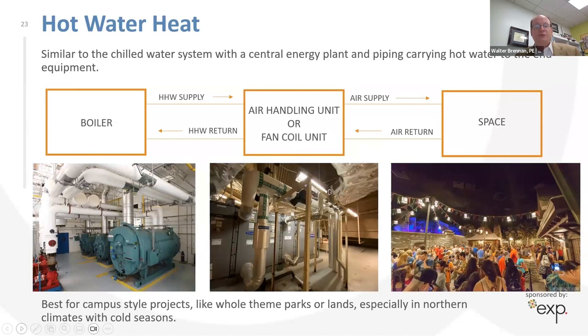Similar to the chilled water system, we also have a hot water system. We have a central boiler that heats up the water anywhere between 120 and 180 degrees Fahrenheit, runs it through an air handling unit. The heat gets taken off the air handler and dumped into your space so it stays warm. The hot water gets cooler, so we have to bring it back to the boiler to heat it back up.